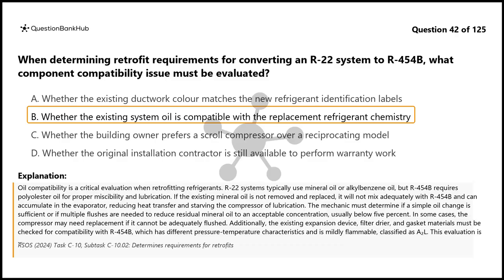The mechanic must determine if a simple oil change is sufficient or if multiple flushes are needed to reduce residual mineral oil to an acceptable concentration, usually below 5%. In some cases, the compressor may need replacement if it cannot be adequately flushed. Additionally, the existing expansion device, filter dryer, and gasket materials must be checked for compatibility with R454B, which has different pressure-temperature characteristics and is mildly flammable, classified as A2L. This evaluation is essential to determining the full scope and cost of the retrofit.